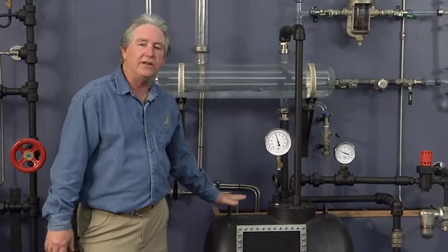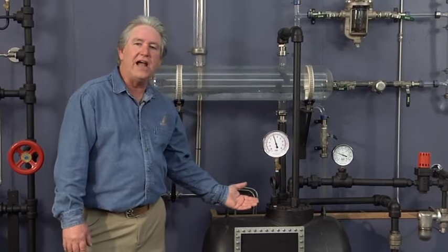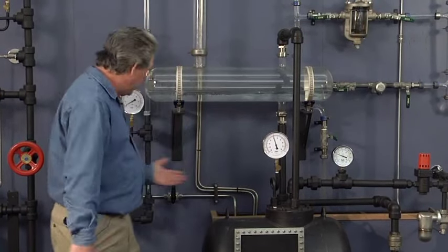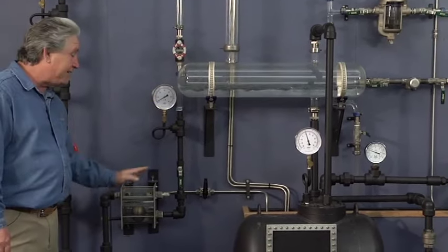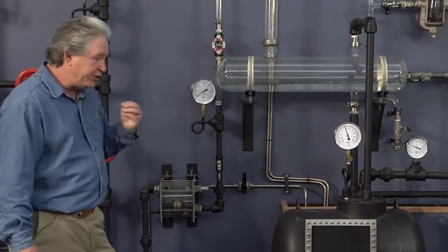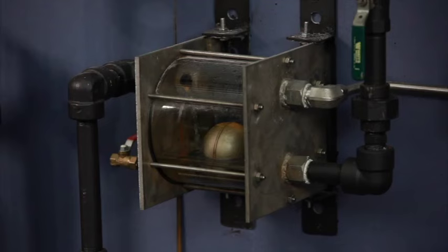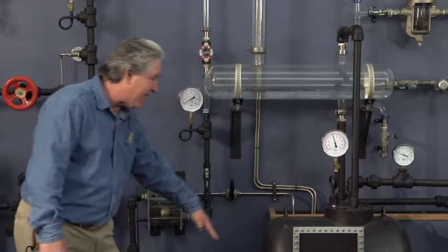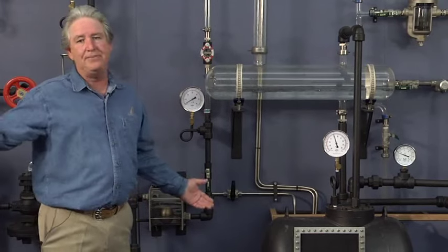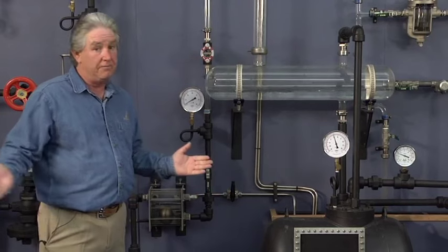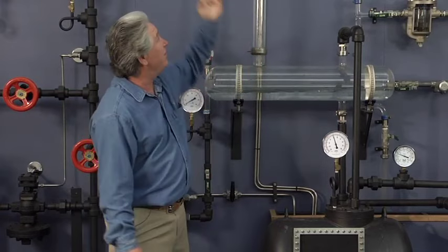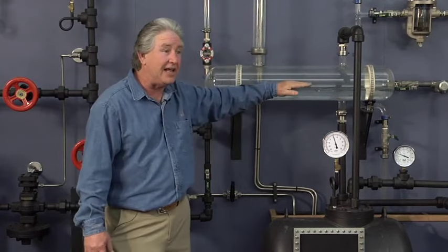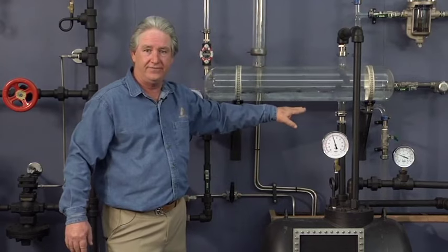Now, the pump out cycle is a fairly long cycle in this demo simply because we wanted you to have a glass trap. Typically, the trap downstream of your pump should be able to take the max condensate rate of the exchanger at a 1/4 pound differential so you don't bottleneck the pump out cycle of the pump. Because what happens when we bottleneck the pump out cycle? Bottom line is it takes more reservoir because I have more time for this to continue condensing and I have to have a place for more of this condensate to gather.